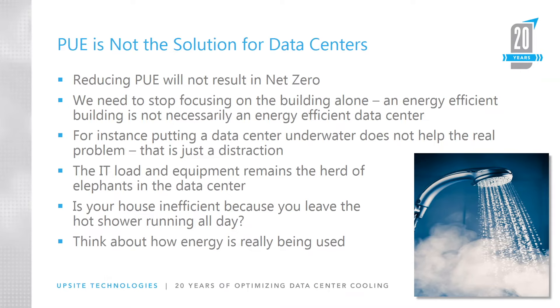All we've got going on in the data center is the hot shower running all day without being used by anybody. We've got IT kit spinning, potentially doing nothing, with very low utilization rates — maybe 15–20%. We have zombie servers not even connected to the network. And yet we're navel-gazing, focused on the building with PUE — absolutely the wrong focus. When it comes to energy efficiency, think about the house and the shower. The most useful thing you can do is turn the shower off and only have it running when you need it. Really think about how your energy is actually being used, not just a proxy metric that isn't representative of what we're trying to achieve as a sector or as a society moving towards net zero.